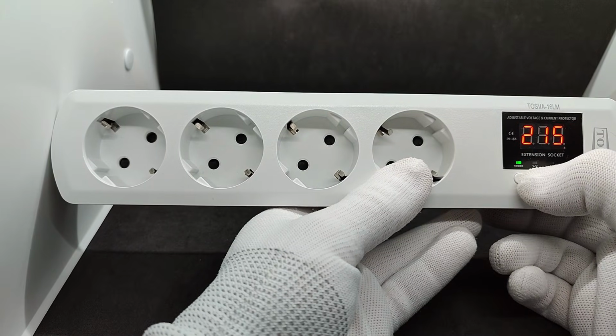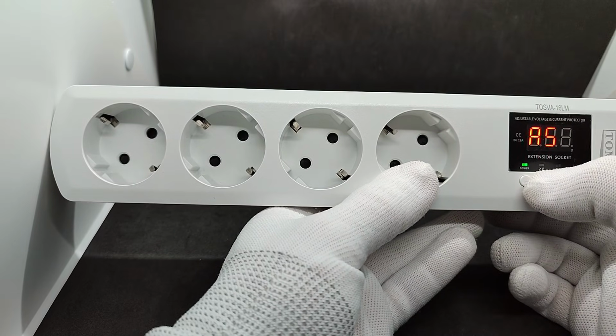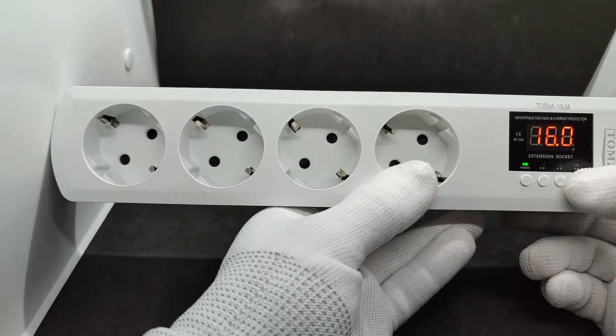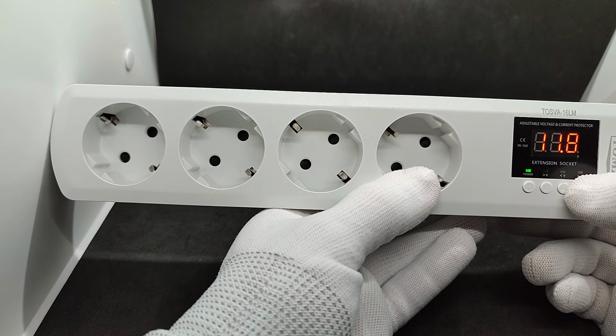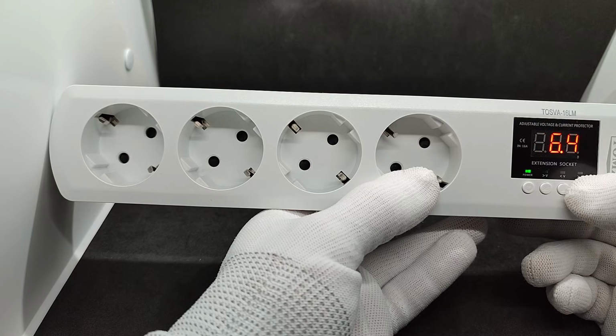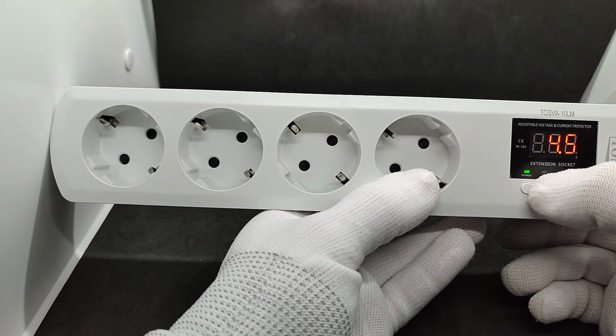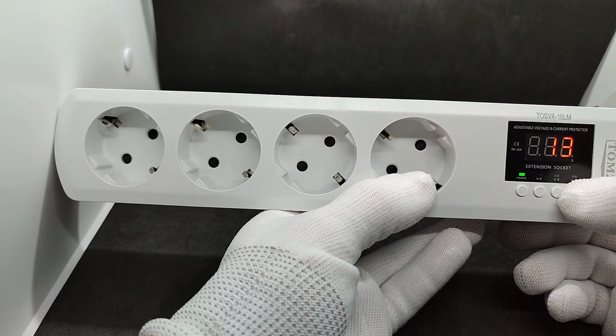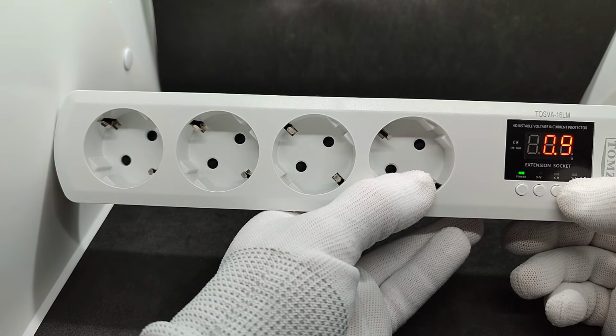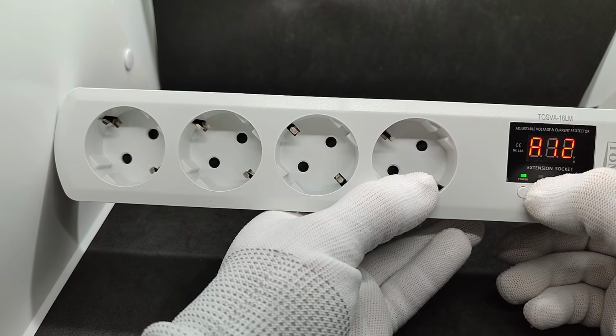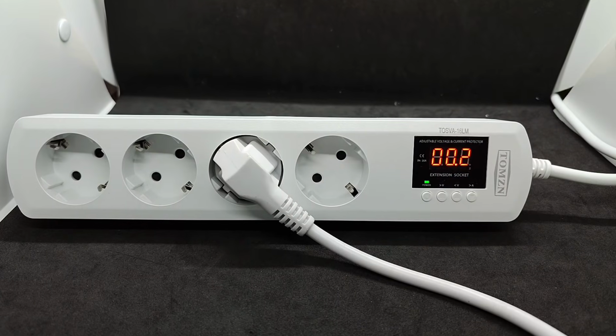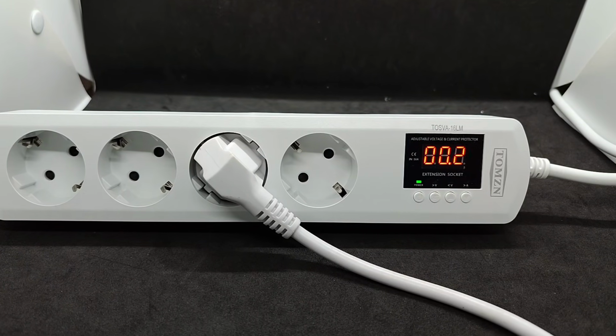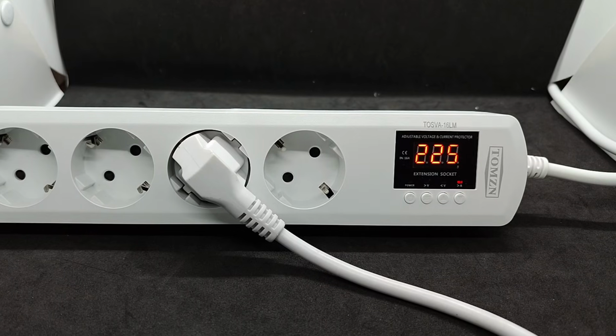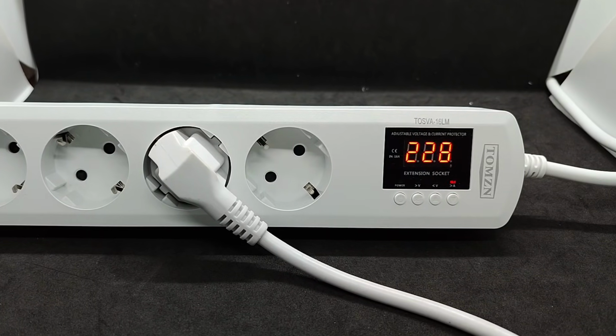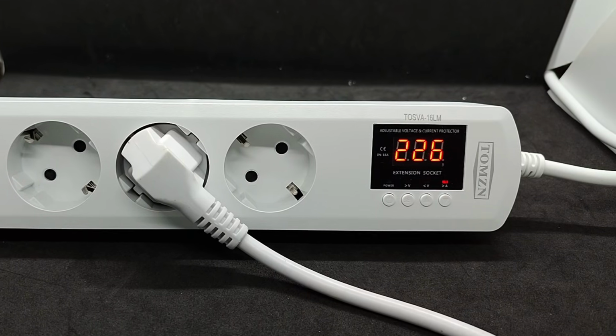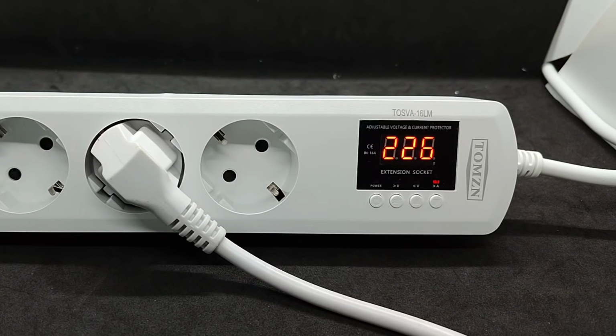For the sake of experiment purity, we will also conduct a test for exceeding the current threshold. As I said, all menu items here are identical to the previous model. Instead of 16, I set it to 4.5 amps so that it reacts to turning on the test load. The turn-on time, or rather the recheck time, is 5 seconds. Shutdown is 0.1 seconds. The operating principle is the same. Overcurrent turns off the relay, then after a specified interval a check is performed. If the load is still higher, it turns off. If not, it turns on. The number of checks can be configured. For an extension cord that has not one but 4 sockets, such protection is more relevant.